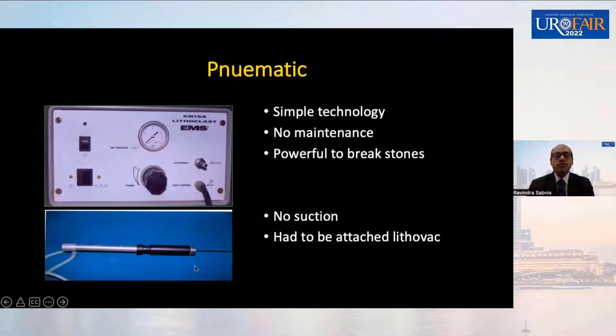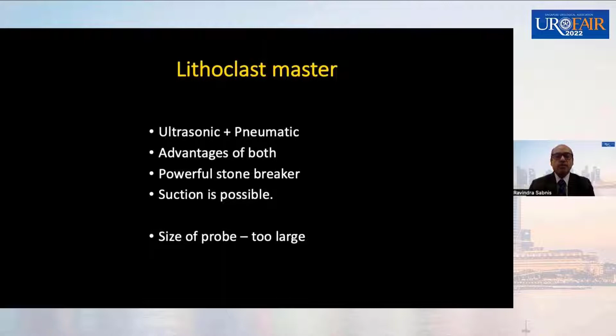LithoClast Master was thought to be a revolution, but unfortunately not so, because it was combining ultrasonic and pneumatic, thinking that there would be the advantages of both sources. Yes, it is a powerful stone breaker and suction is possible, but in combining both, the size of the probe has become too large, and because the LithoClast probe sits inside the ultrasonic probe, the lumen gets compromised, and therefore the effectivity goes down.